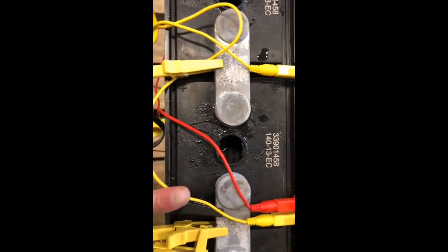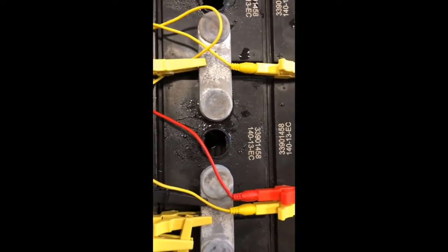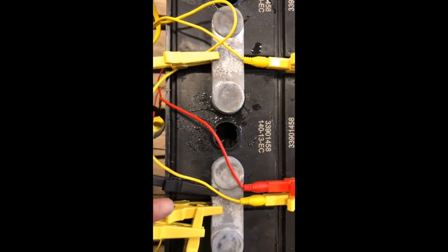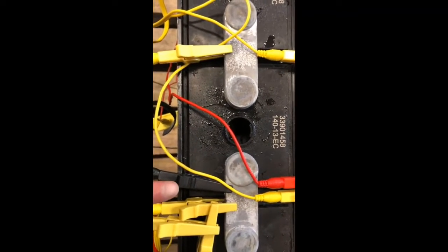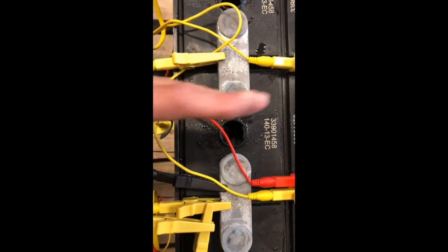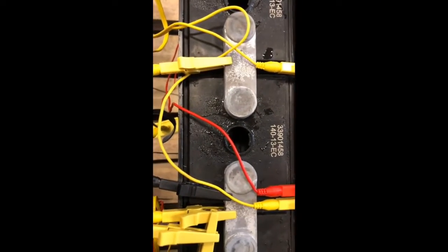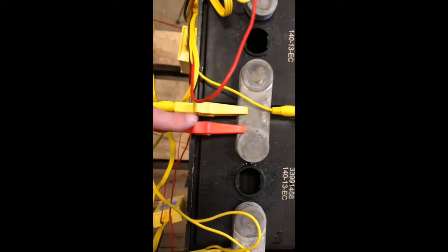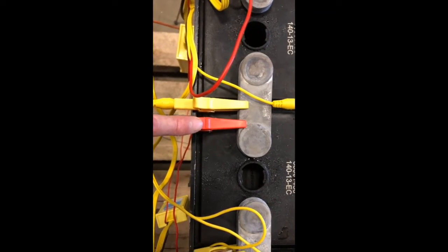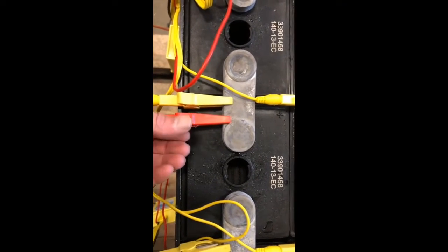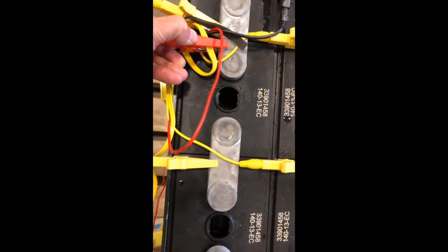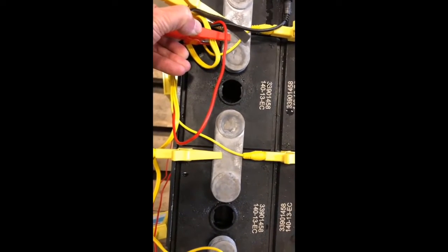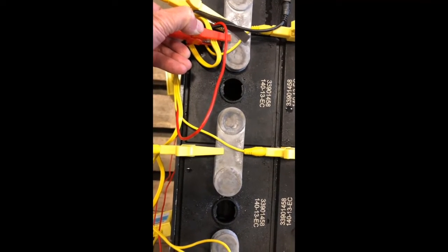If during testing you have to jumper out a cell in the middle of 4 modules, it will reduce the power to the module by 2 volts. When I break these intercell connectors, I have to take my power supply voltage for that module and move it 1 additional intercell connector to give me the additional voltage needed to power the module back up.